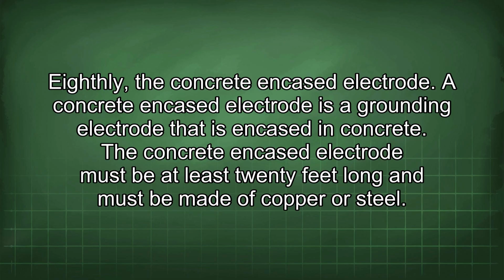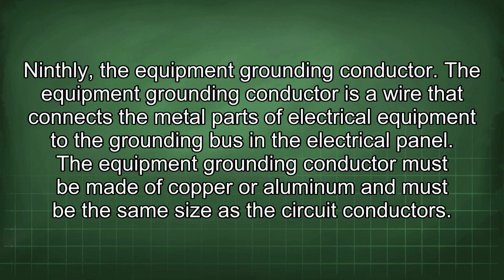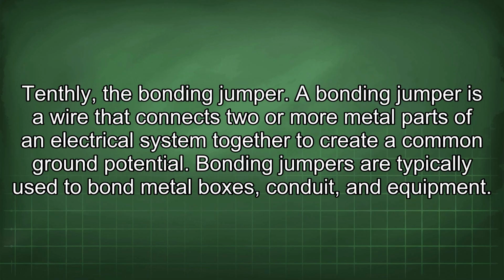Eighthly, the concrete encased electrode. A concrete encased electrode is a grounding electrode that is encased in concrete. The concrete encased electrode must be at least 20 feet long and must be made of copper or steel. Ninthly, the equipment grounding conductor. The equipment grounding conductor is a wire that connects the metal parts of electrical equipment to the grounding bus in the electrical panel. The equipment grounding conductor must be made of copper or aluminum and must be the same size as the circuit conductors. Tenthly, the bonding jumper.